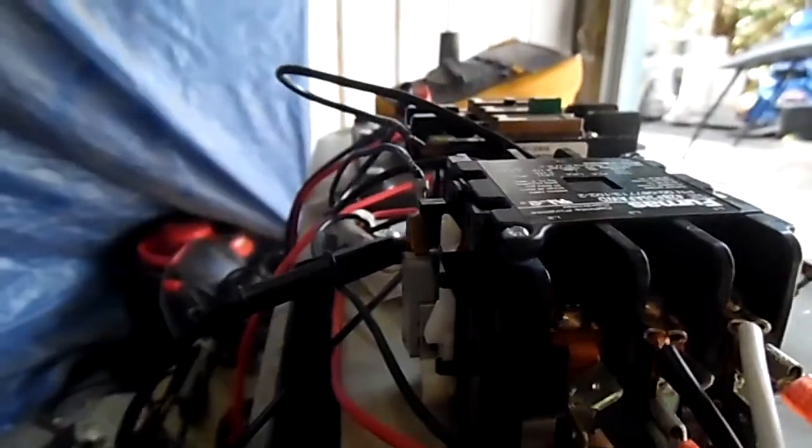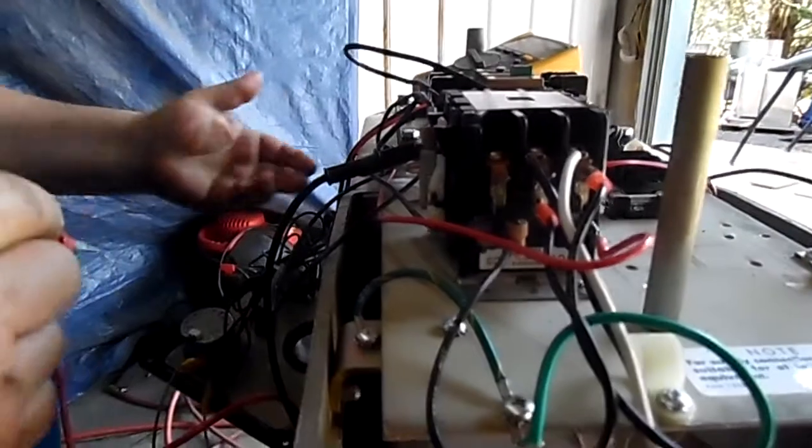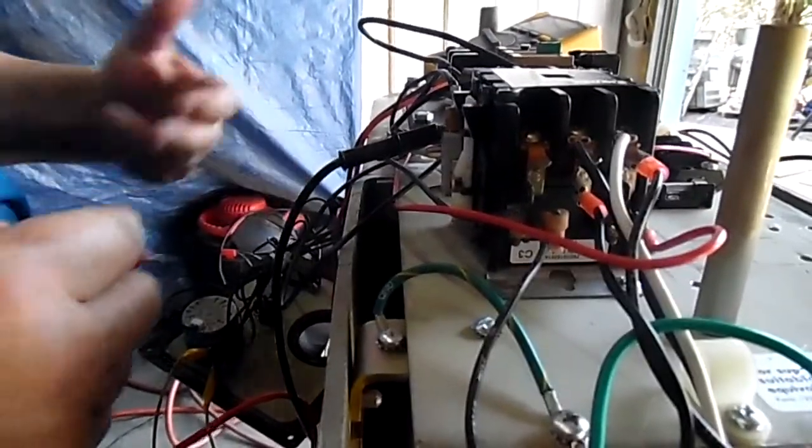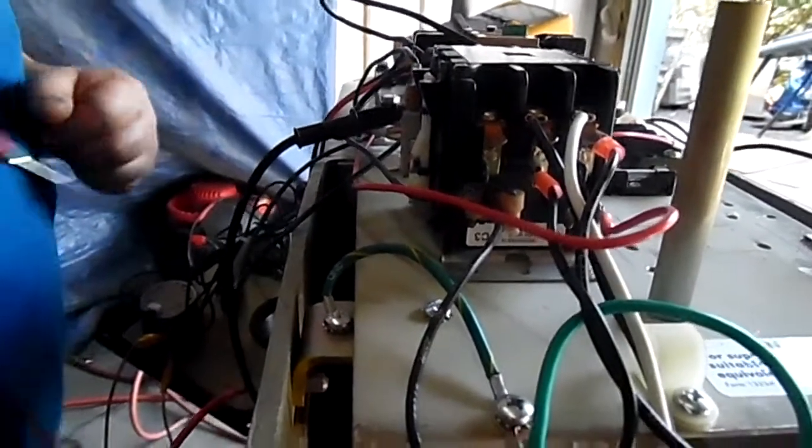I'm going to test the individual circuits. Normally a safety goes bad, or switch, timer, or buttons. Usually not the motor or the contactor. It's usually a switch or wires come loose.